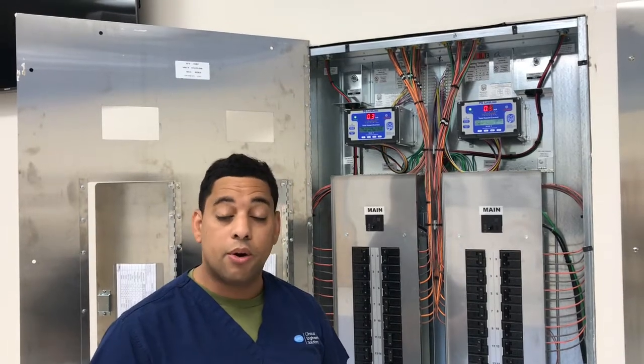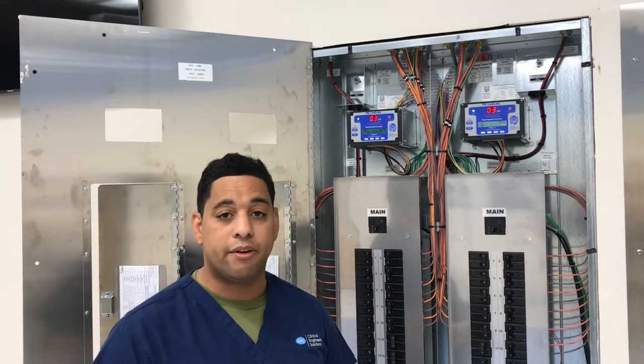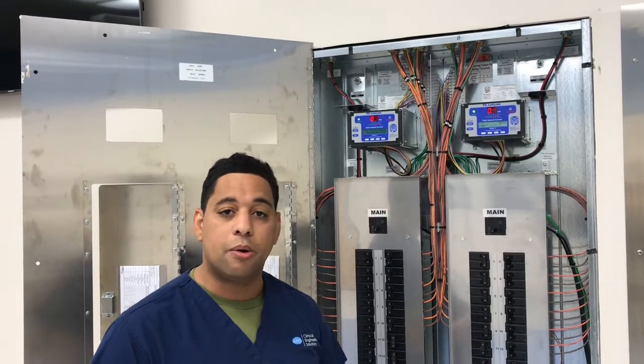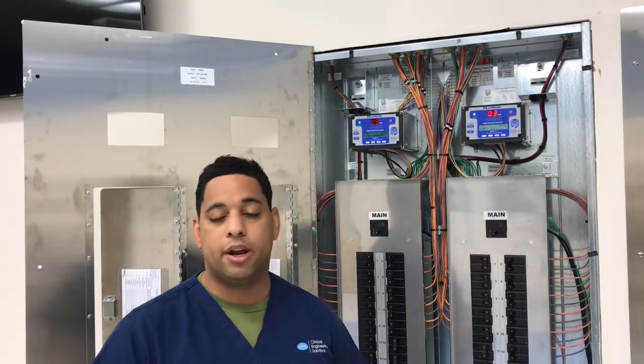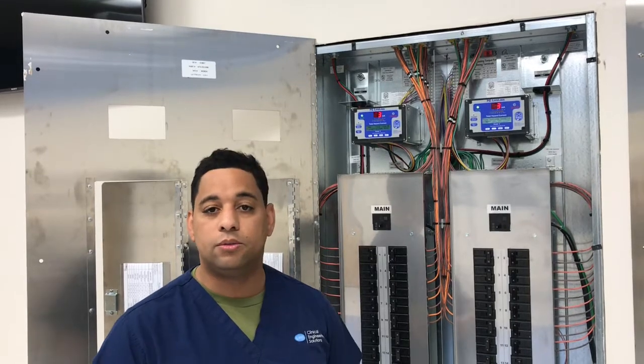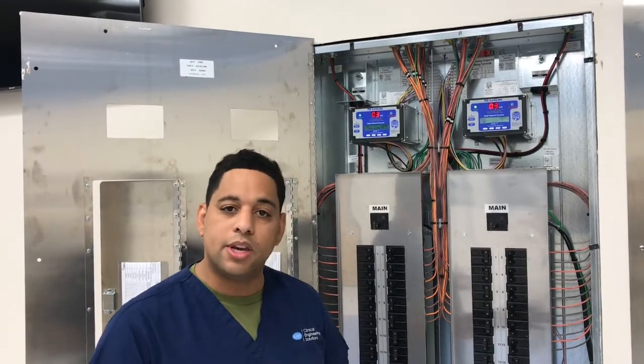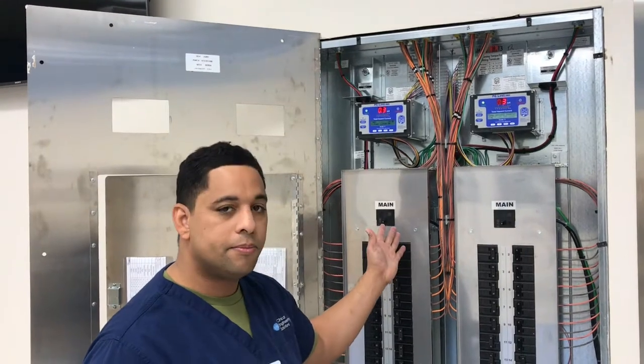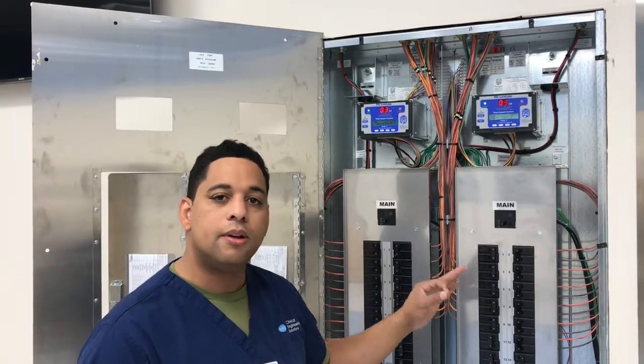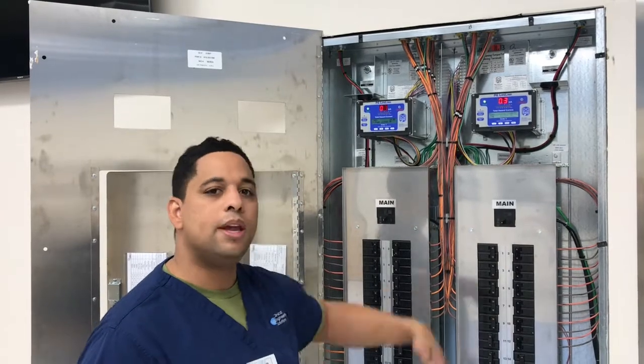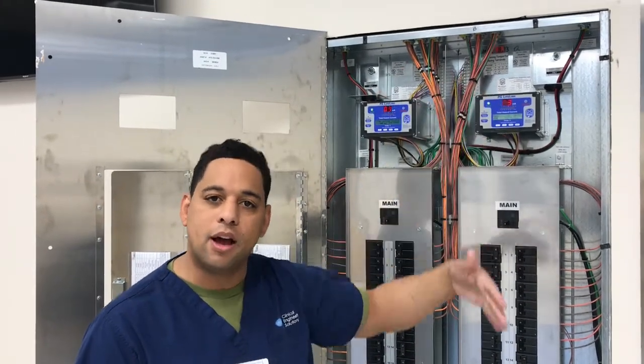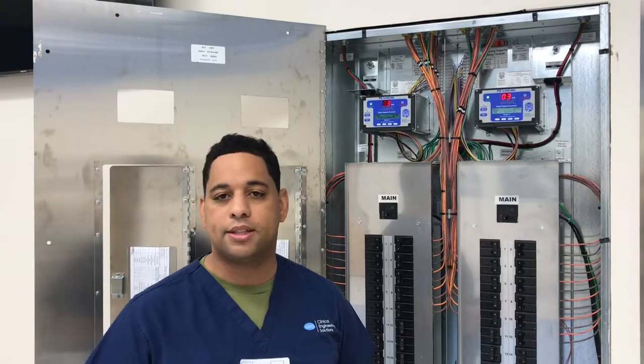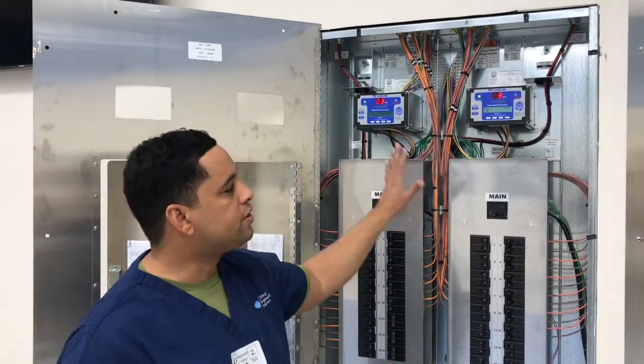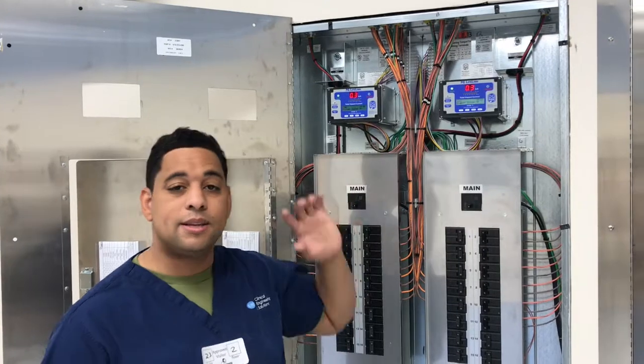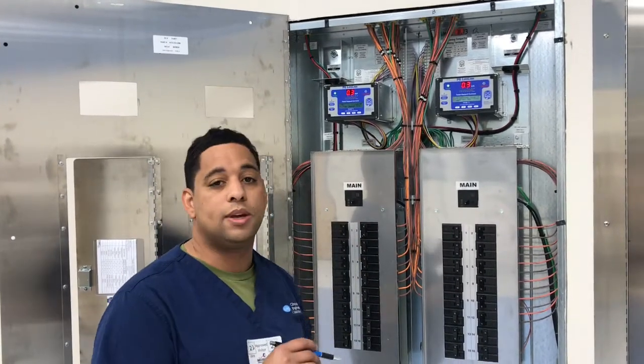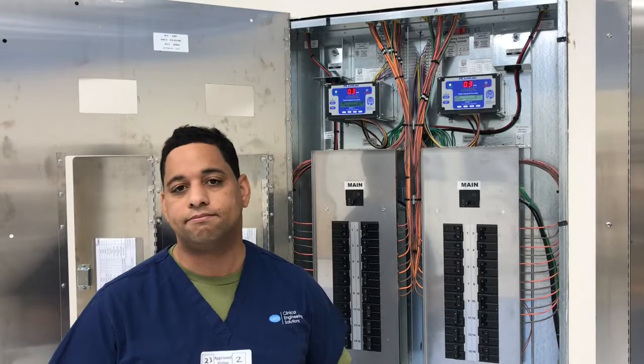An uninterrupted power supply has a large battery in it. And when plugged into power, it charges the battery. If the battery is full, it dumps the power that it doesn't need. And this system senses that power dump to be leakage. And so it may go up and alarm and then come down and shut off. We see that all the time. It doesn't mean that there's anything wrong with the system. It simply means the device that was connected to it is triggering the alarm.